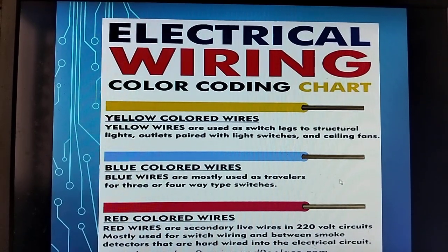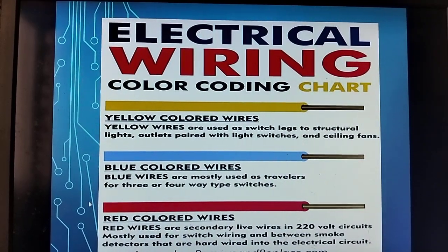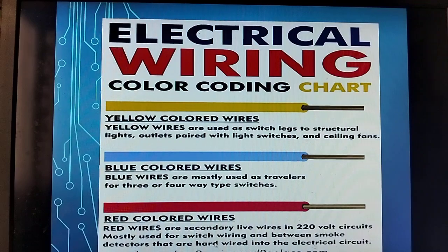If we are using these three-way switches, four-way switches, these are used for travelers, because in stairway lamp installation there is a common line and then travelers, and then line 1, line 2 for the power supply. Red color wires are secondary live wires in a 220-volt circuit, mostly used for switch wiring and between smoke detectors that are hardwired into the electrical circuits.